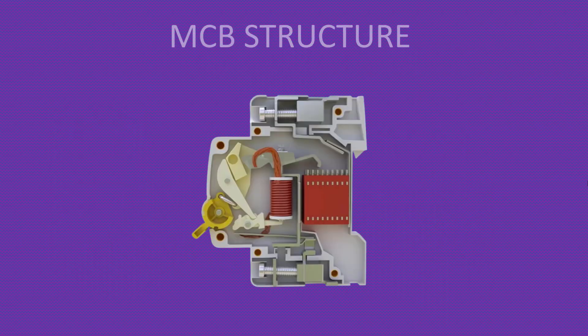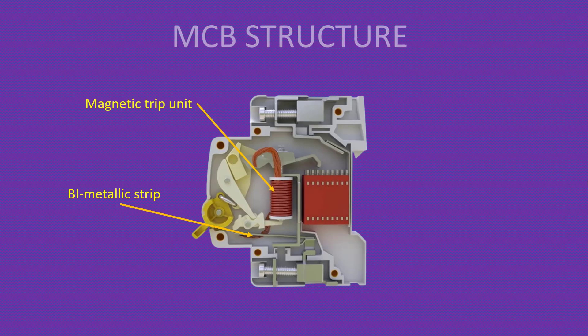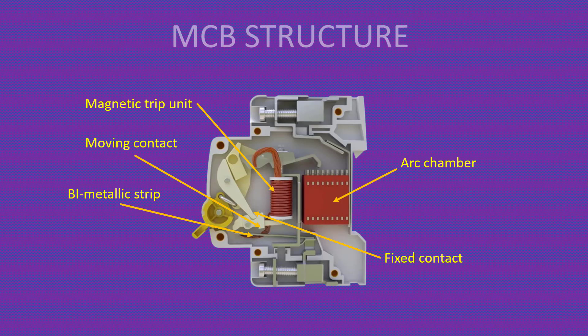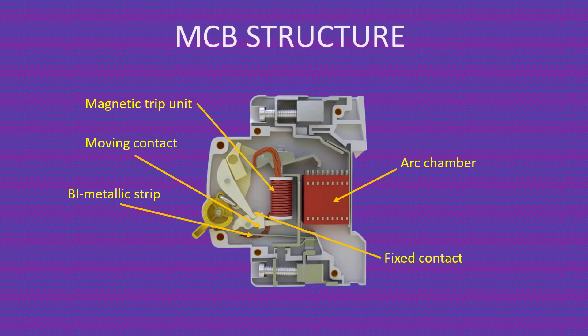If you look at the MCB structure, it has a bimetallic strip and a magnetic trip unit. The magnetic trip unit consists of a coil and a piston arrangement. Then it has a fixed contact, moving contact, and an arc chamber. The arc chamber is used to quench the arc due to sudden switching or sudden interruption of current. If you turn off the current suddenly, there will be a spark or arc due to ionization of air. The arc chamber has different small chambers, so the arc is forced to pass through them and loses strength until it is extinguished.